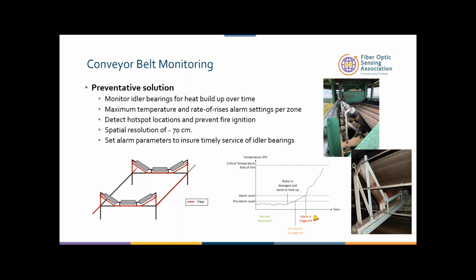Conveyor belt monitoring is an interesting one. We get a lot of fires because the idler bearings overheat, and these bearings can cause a lot of damage because once a fire is there, you have a wood pellet or a different type of material that can catch fire. The ability to monitor the temperature using the fiber optic linear detection: you have the cable that can go around the bearings and then come down and go to every structure. Each one of those bearings can be monitored.